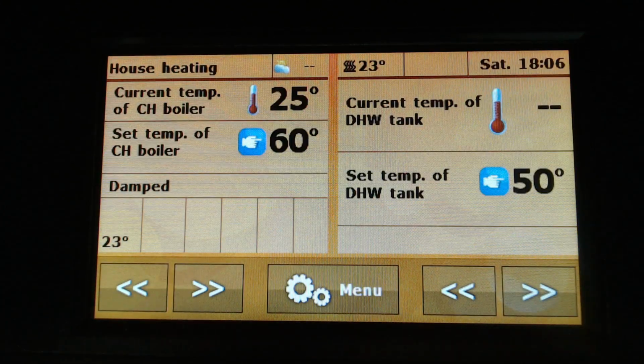So you basically make sure that the power is always on the selected value. When we selected 30 kilowatt and activated feeder calibration right now, we are sure that the pellet dosages correspond to 30 kilowatt of power. Of course, when you start the boiler for the first time, I always recommend to wait a little bit for the flame to adjust and then check the flame physically, because you want to make sure that the combustion process is all right.